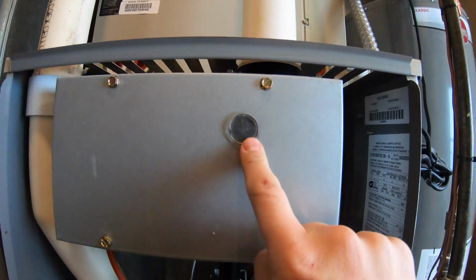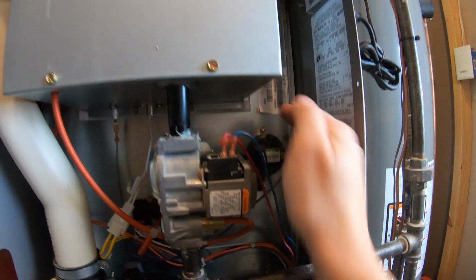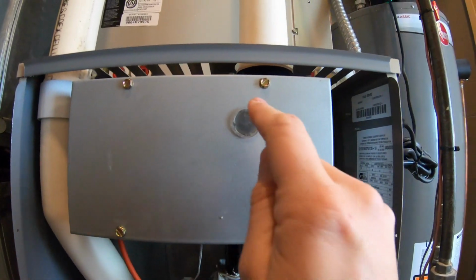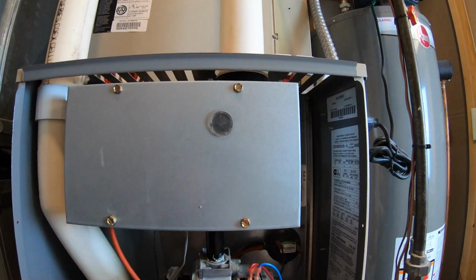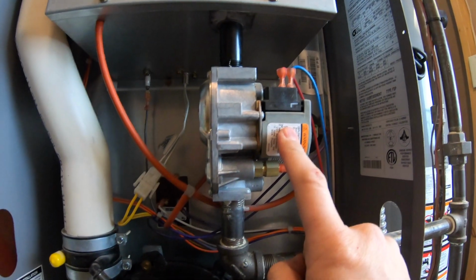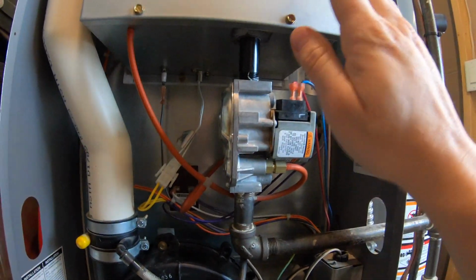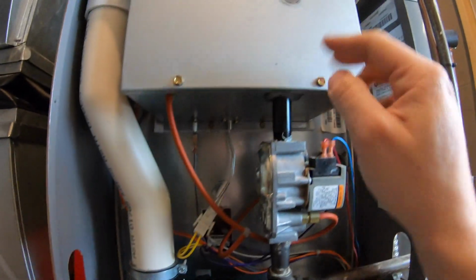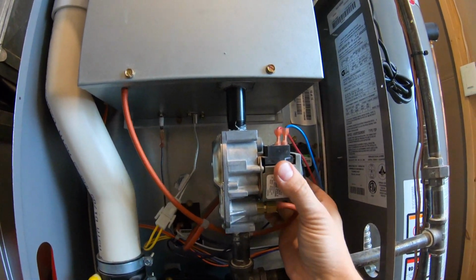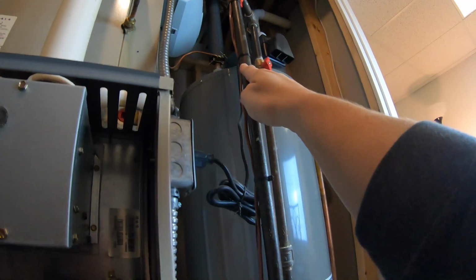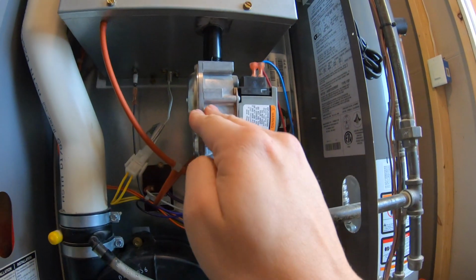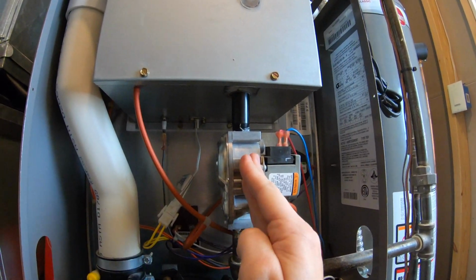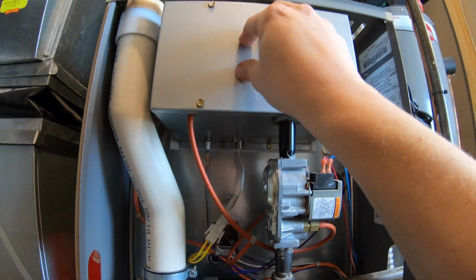So if you peek in through this hole, this motor's running, this switch is closed, and this has power going to it, you should see an orange light here. And then this gas valve's gonna open. So once this igniter has had a moment to warm up, this gas valve is going to open to allow gas to flow through this line here, through the gas valve at a specific pressure to the burners that are behind this cover.